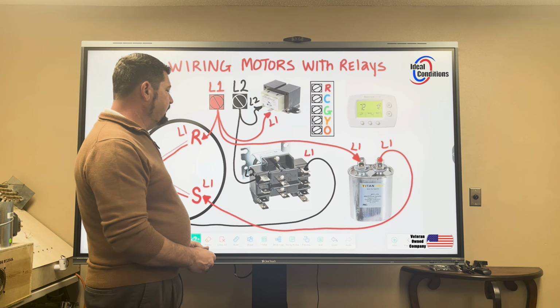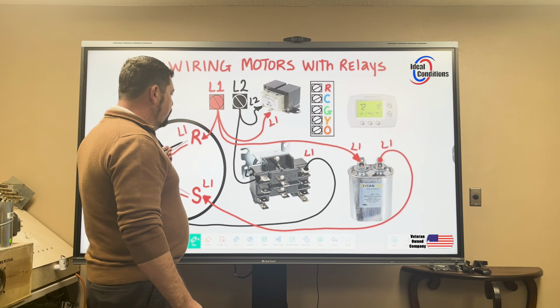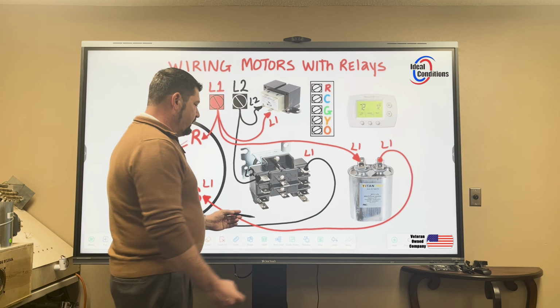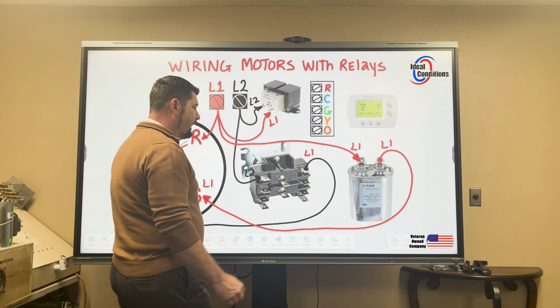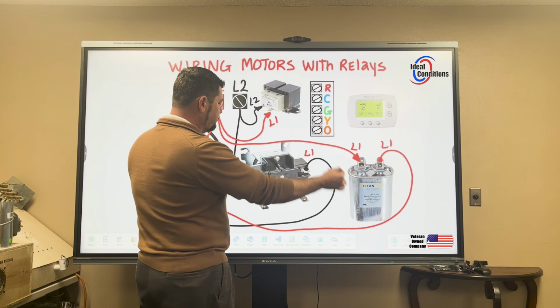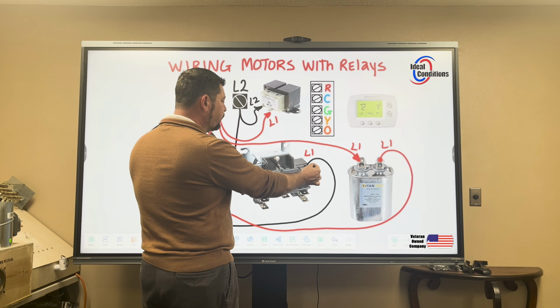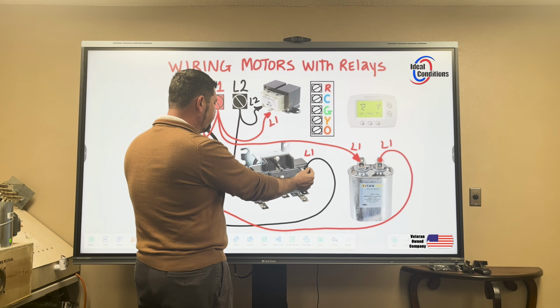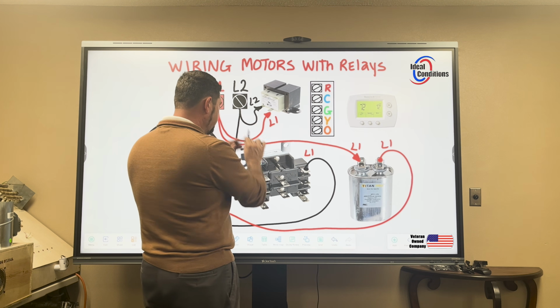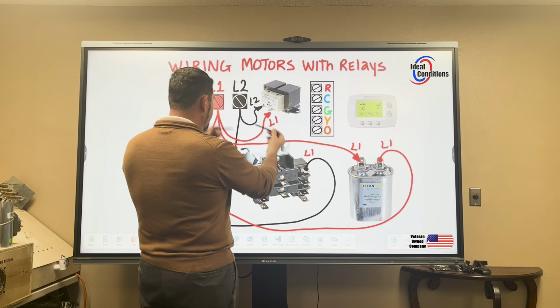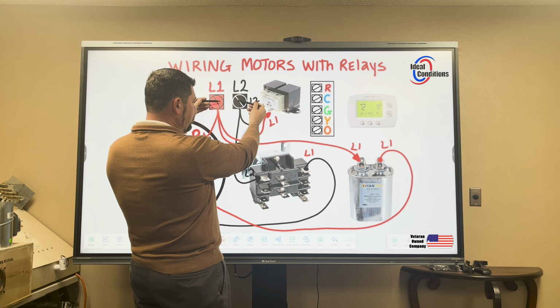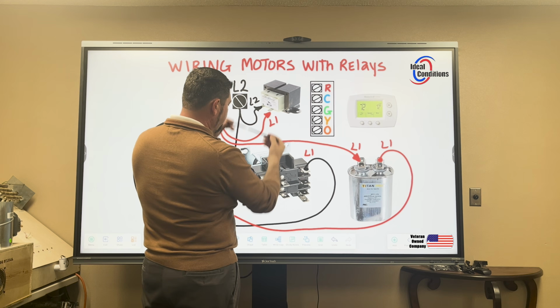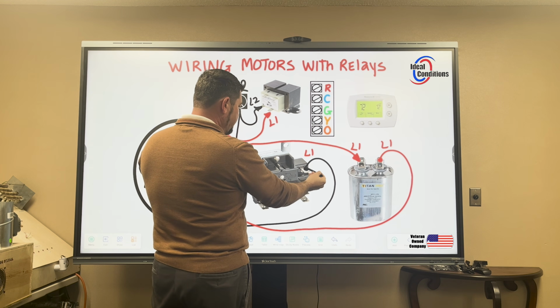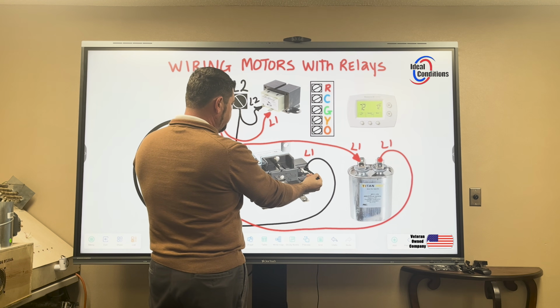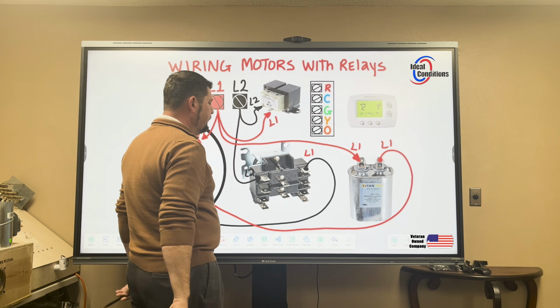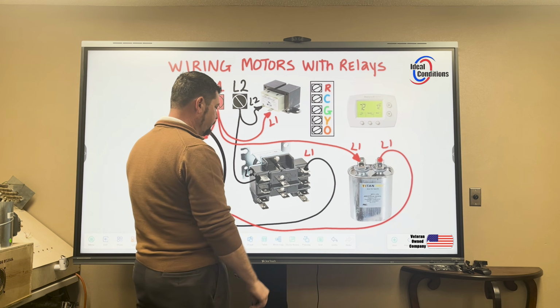So if I wanted to see why my motor is not running, I don't have any 24 volts on my relay. I could come up between terminal 1 and terminal 3, and I should read the difference between L1 and L2. We're going 2 different ways here. So if I went up here and I read 240 volts, and I read 240 volts here, then I'm also going to read 240 volts here, because I'm reading L1 and L2. And so I know my relay is not closed.